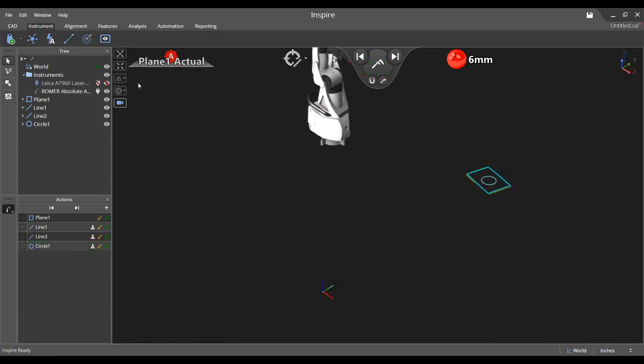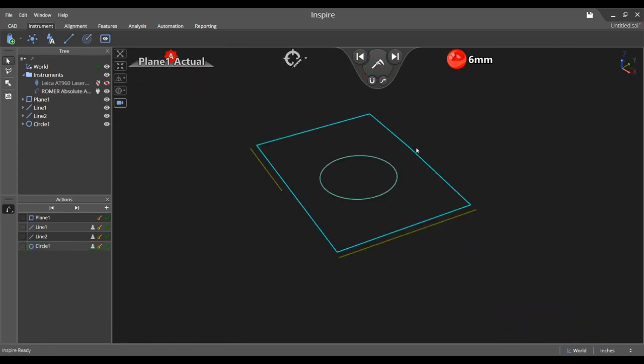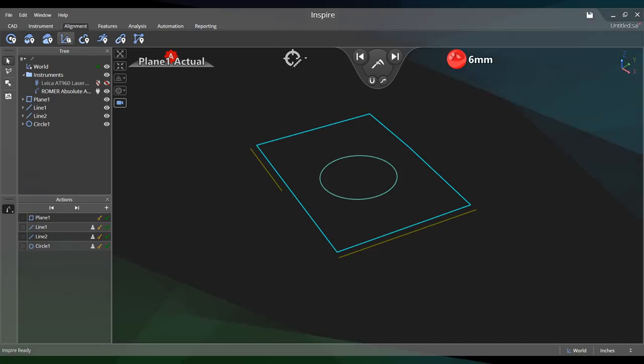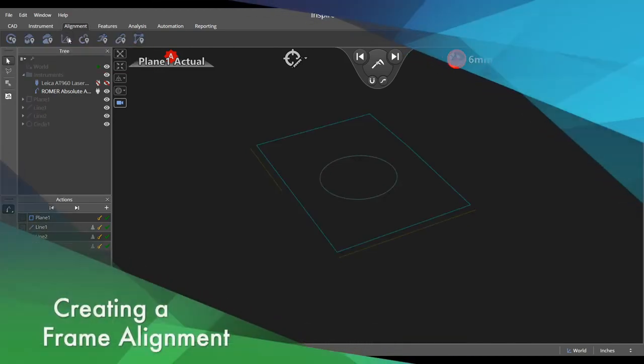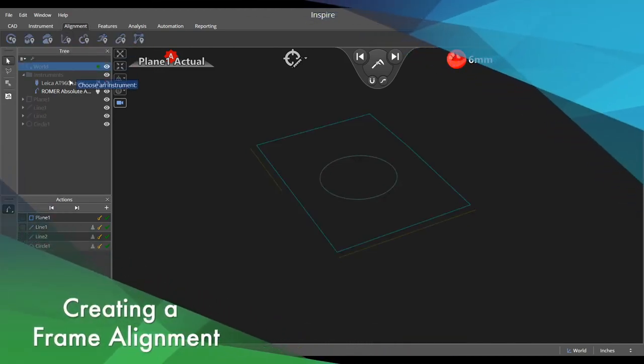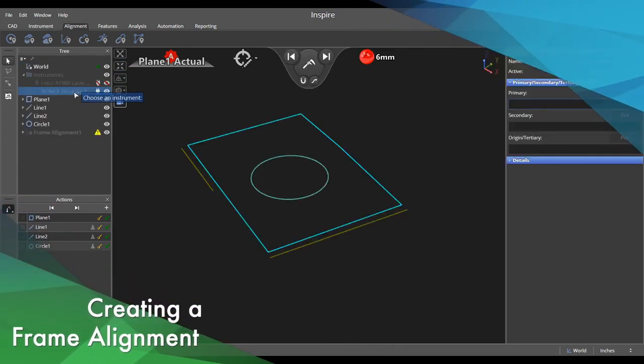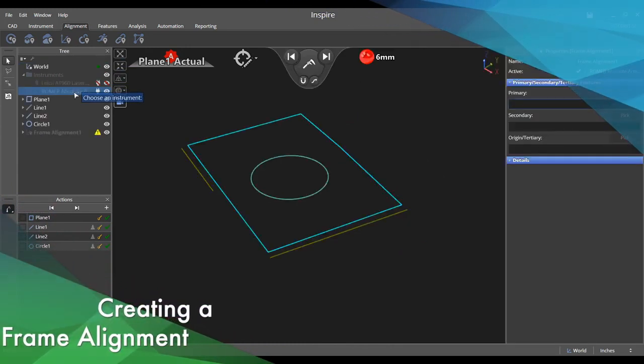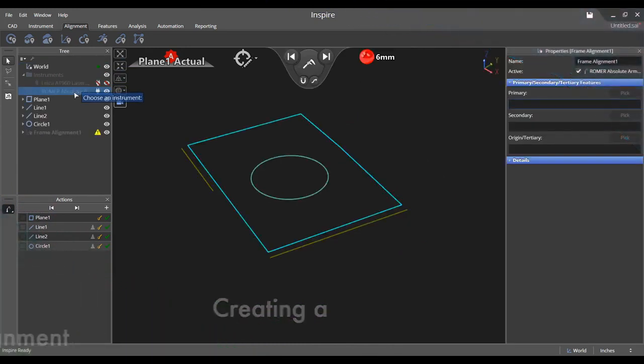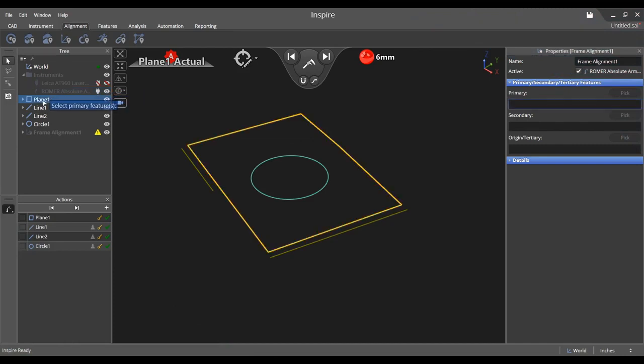Next, let's establish a coordinate system from the measured features and utilize it to align to a nominal frame. Navigate to the alignment tab and choose frame alignment. Notice the properties panel appears to the right as well as a prompt which allows for selection of the primary, secondary, and tertiary features of the measured frame.